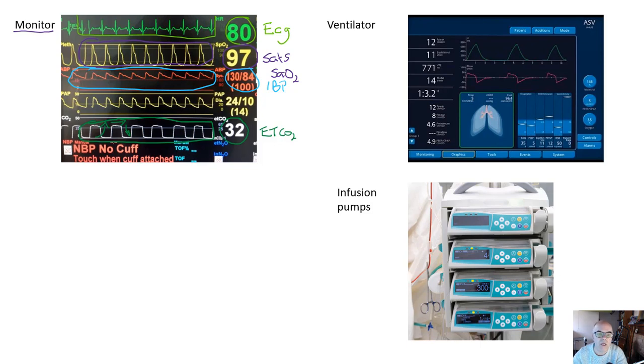Okay, so that's the monitor. They're the common things you see on the monitor. They're alarming a lot, and one of the pieces of advice I give to any ITU nurse is to decide what you're willing to tolerate with your alarms. So if they're banging away at 110 and they have been for hours and we're not doing a great deal about it, it doesn't make any sense to have your alarm rate set at 105. Because it's just going to alarm constantly. You're going to be pausing it constantly. You're not doing anything about it, so you don't need to be told about it. So, for example, you would set your alarm rates maybe at 115 to 120. So be aware of your alarm limits as well. And obviously, if you don't work in critical care and you're one of those lovely people who've come to help us out, then be advised from your ITU nurses.